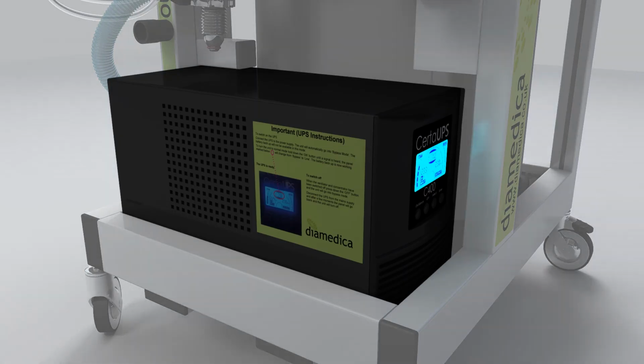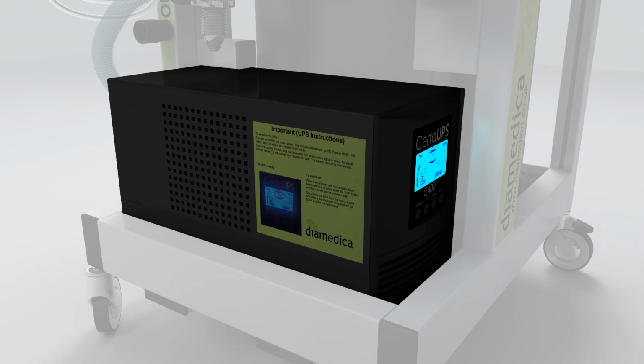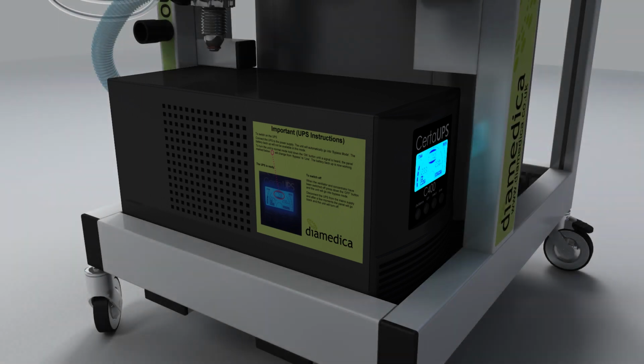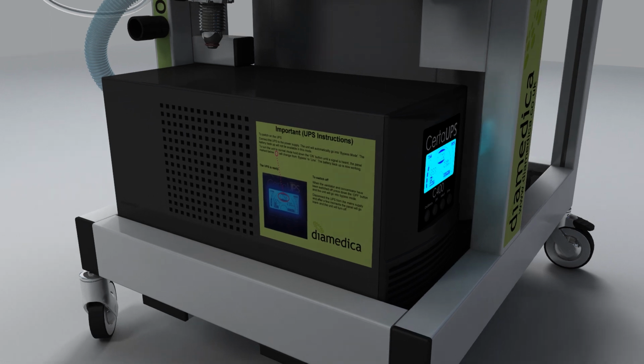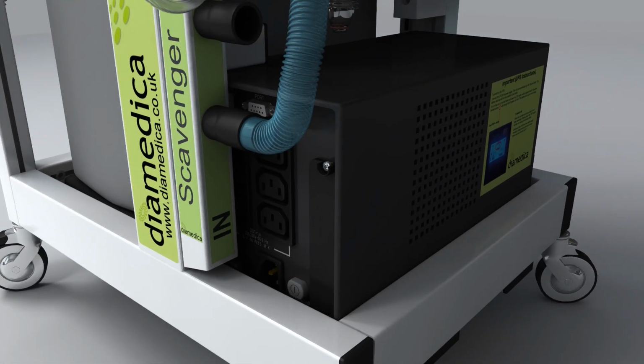Connect the power lead and turn on the UPS. When the UPS is running in normal mode, it serves two functions. First, it acts as a voltage stabilizer to provide a constant, safe power supply, protecting against power surges that could damage the equipment. It will accept voltage from 160 to 300 volts. The second function is to provide battery backup support for the entire system, providing full functionality including the oxygen concentrator.